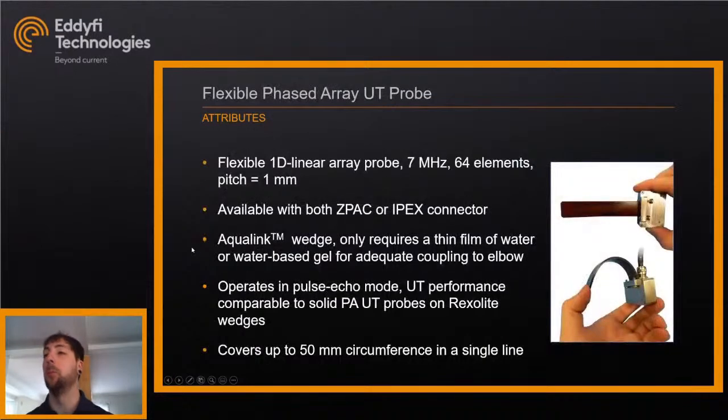The scanner is used with a flexible phased array UT probe: a flexible 1D linear array, 7 MHz, 64-element, 1 mm pitch. It's available with both the Z-Pack connector or the IPEX connector depending on the instrument. It's typically coupled with an Aqualink wedge, so instead of a bubbler with a column of water, it only requires a thin film of water or water-based gel — requiring much less couplant to get adequate signals. It operates in pulse-echo mode, and UT performance is comparable to a solid PA probe of similar size. It covers up to 50 mm or 2 inches of circumference in a single scan line.